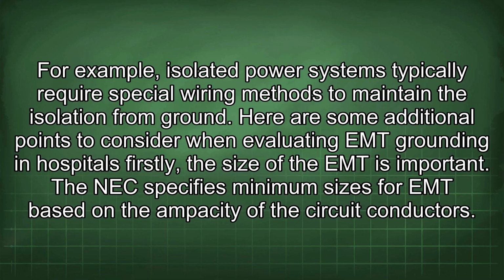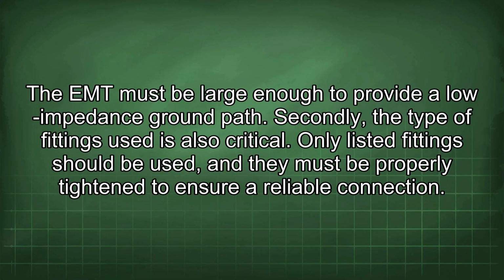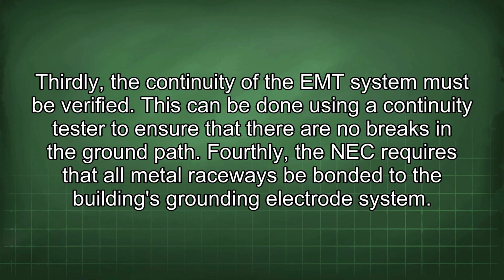Here are some additional points to consider when evaluating EMT grounding in hospitals. Firstly, the size of the EMT is important. The NEC specifies minimum sizes for EMT based on the ampacity of the circuit conductors. The EMT must be large enough to provide a low impedance ground path. Secondly, the type of fittings used is also critical. Only listed fittings should be used, and they must be properly tightened to ensure a reliable connection. Thirdly, the continuity of the EMT system must be verified. This can be done using a continuity tester to ensure that there are no breaks in the ground path.